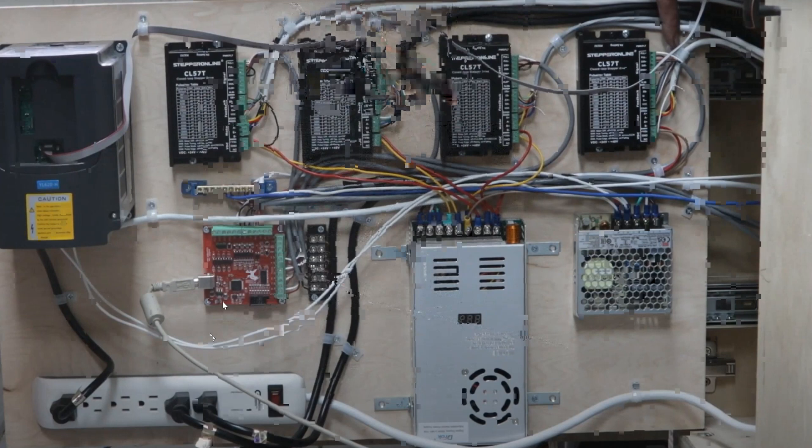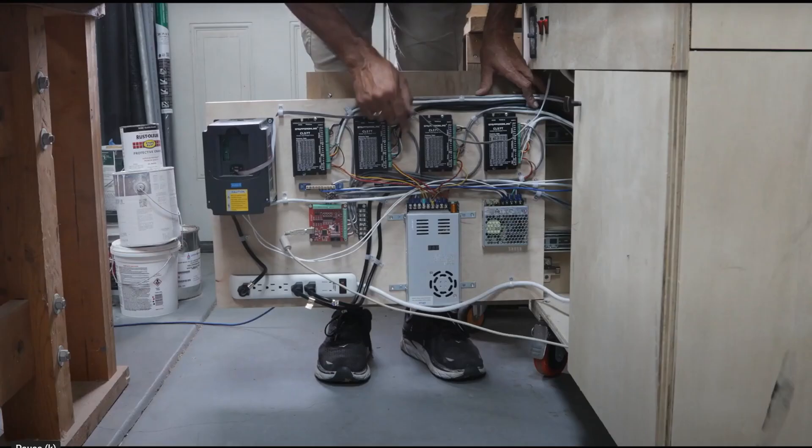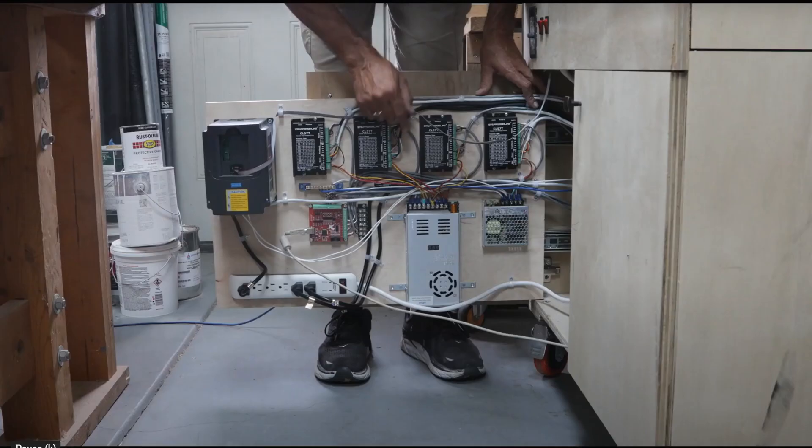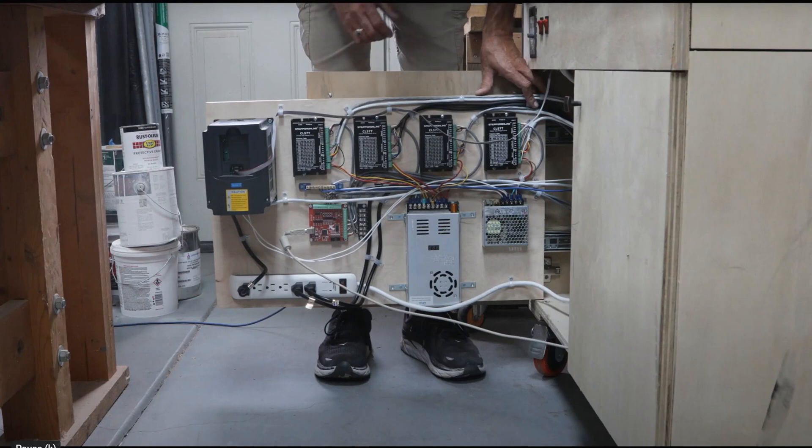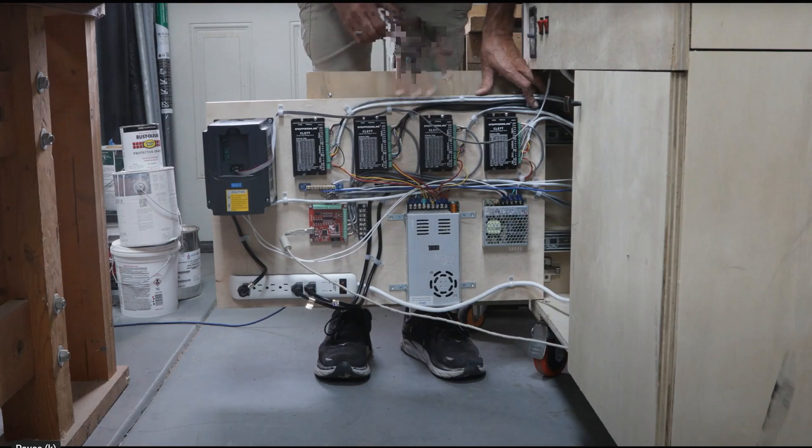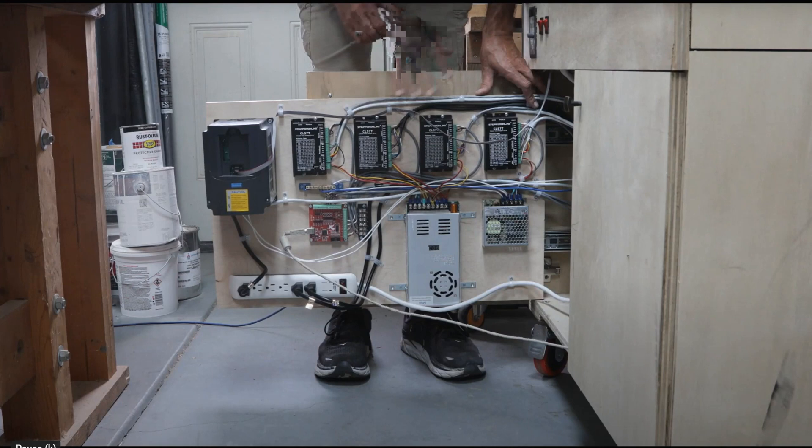So I replaced all of them and it requires two sets of wires. One is a four conductor shielded wire which is this gray cable here, and then the other is a six conductor shielded wire which is this white cable here. The four conductor powers the motor. The six conductor cable is the feedback controller. As you can see I think it's important in a case like this to keep all your cables organized. I have them connected with little wire ties to the board just to keep things organized so I know where everything goes and if there's a problem I can always diagnose. He can always diagnose it, which again if there's a problem, to me as a logistical person doing this as I've done it now professionally for over a decade, if I don't document and I don't have labeling done on everything, I don't know what I'm working on guys. And I'm just telling you, and I don't care if this is the only system you're building, take your time, label everything as much as possible.